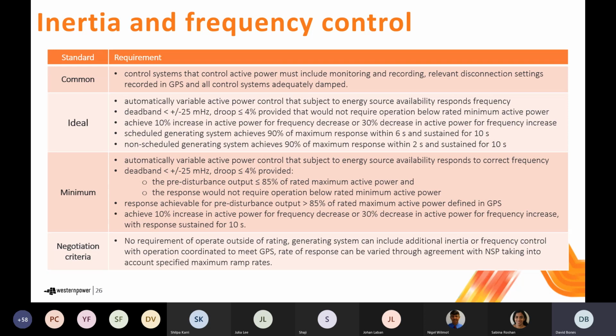You need to be able to respond to correct frequency deviations and to have a 25 millihertz deadband and a response consistent with a 4% droop. And that's provided that at the time the disturbance arose, you were operating below 85% of your rated output and that the response didn't drive you below technical minimums. The GPS requires that, although you don't have to meet that particular 4% droop requirement above 85% output, the capability to respond above 85% output is actually recorded in your performance standard.